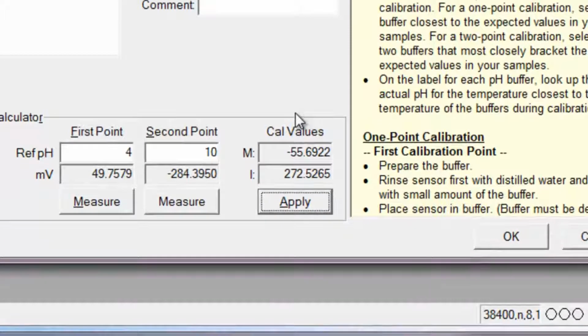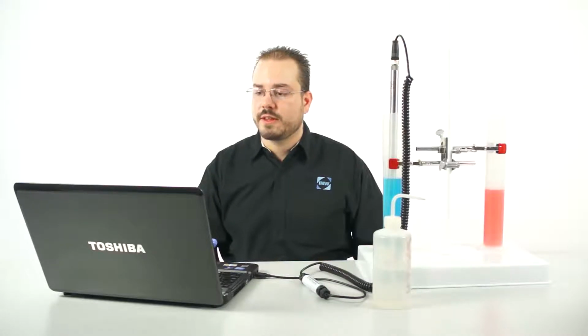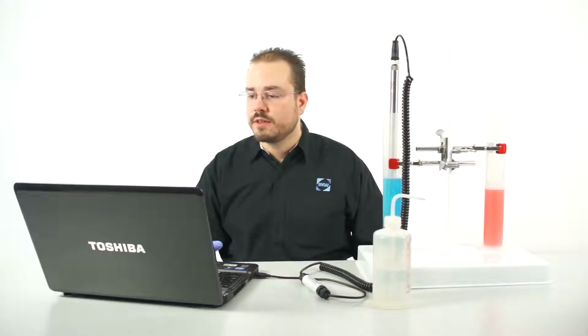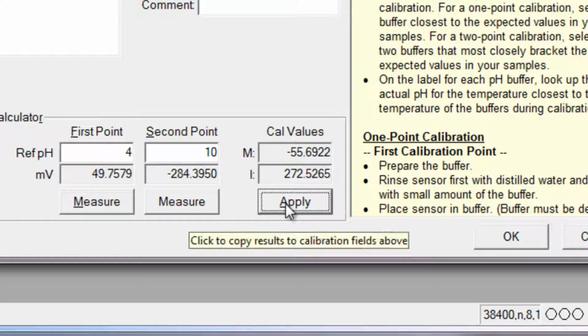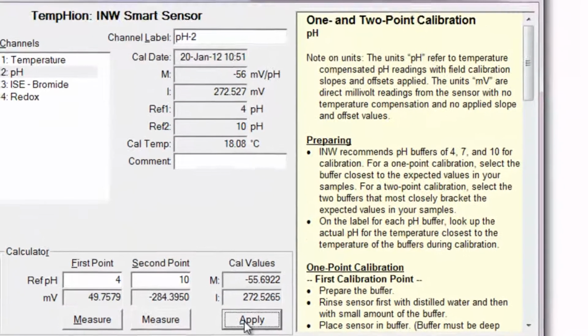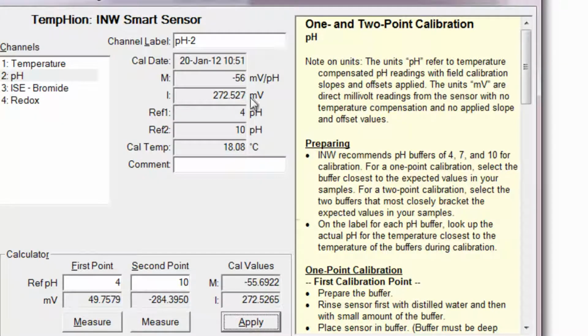And what you'll see on the screen is an M and an I value. And that'll represent your slope and your offset. For pH, we'll want to see an M between -50 and -60, and an I above 240. If your values come outside of that range, you want to repeat the calibration process until you get the values in that range.